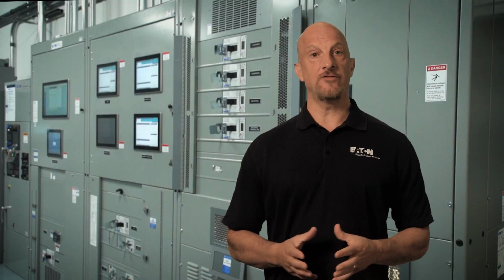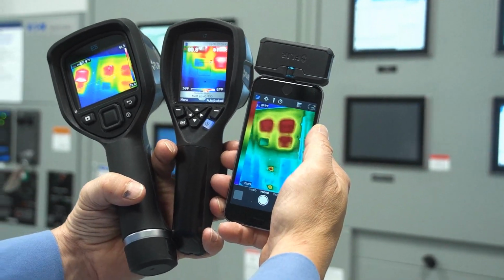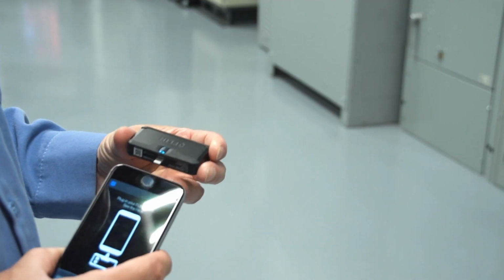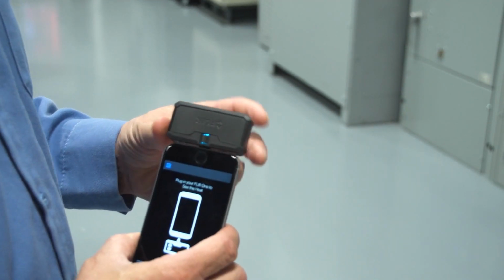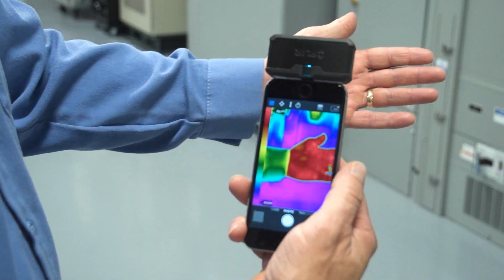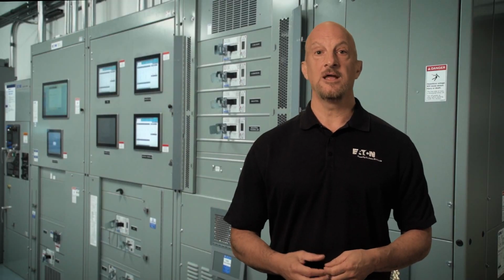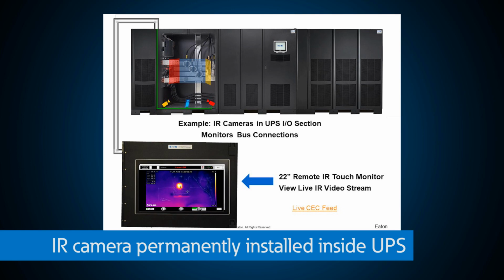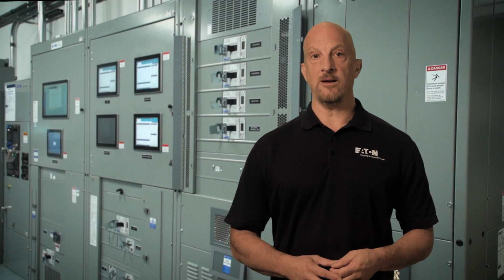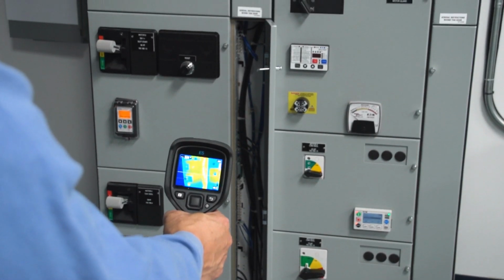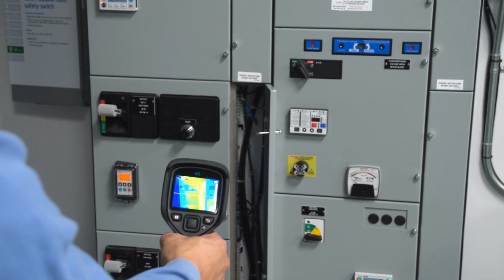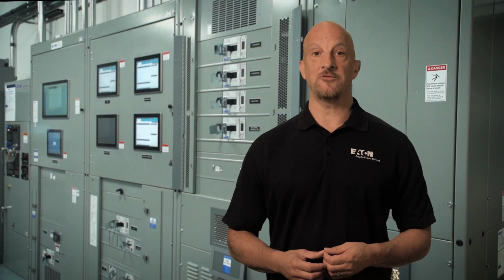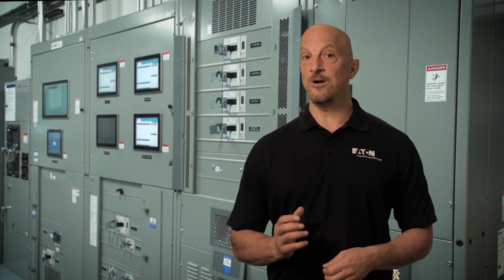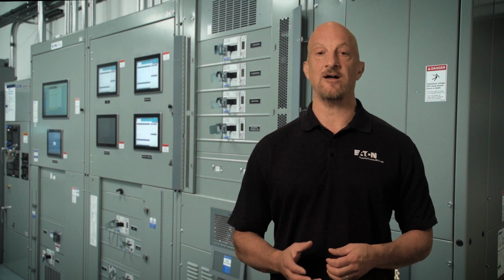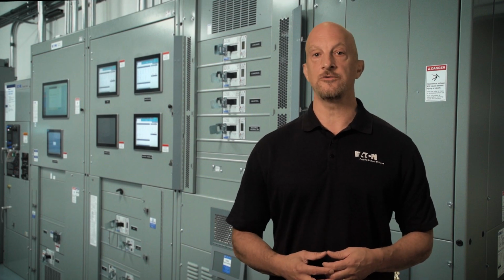Today, the cost and form factor of the cameras has changed by an order of magnitude or more. You can now connect a small IR device to your phone and obtain very good resolution images of your equipment. In some cases, the equipment is so inexpensive that it makes more sense to have it permanently installed inside your equipment for critical loads like UPS or some switchgear. The portable cameras are much more portable, and with a good battery can last much longer than you would need for a typical maintenance scan. Sure, you can still buy a very expensive camera that has lots of bells and whistles, but I'm pretty sure you'd have a hard time finding one that's $65,000 like the ones I bought all those years ago.